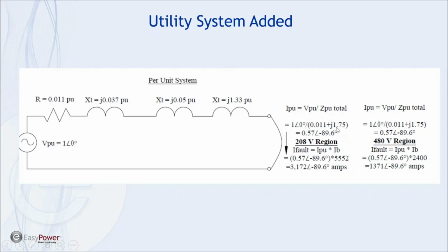Now, because we have some resistance and reactance, we're going to get a slight angle. But if you notice, we're only at 89.6 degrees. We're not far from 90 degrees, which would indicate completely reactive. Multiply that in the 208 volt region times 5552, and we now get 3172. And before we had gotten 5329. So in this case, it had a fair impact on the available fault current. That's another illustration, I think, of the importance of getting system information, because it can reduce the fault current.